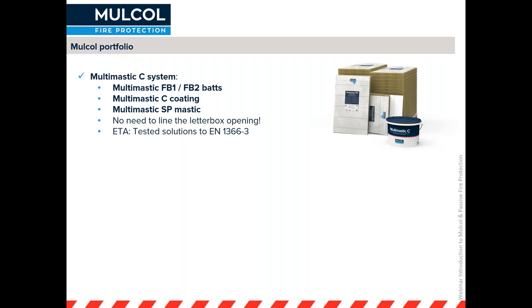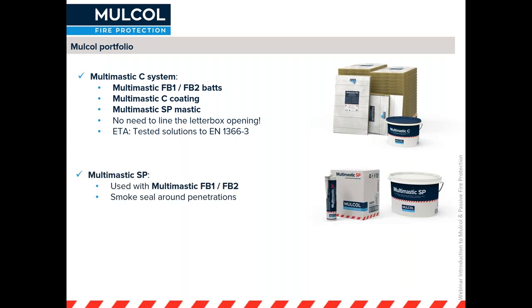Now, one of the differences with our coated board system is that you do not need to line the letterbox opening with a plasterboard. And of course, like all our products, this has an ETA, a European Technical Assessment. So it has been tested to EN 1366-3.